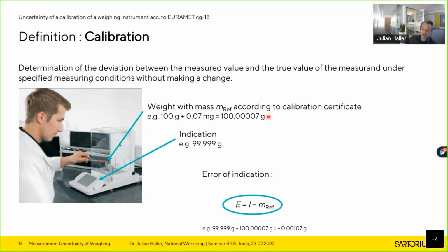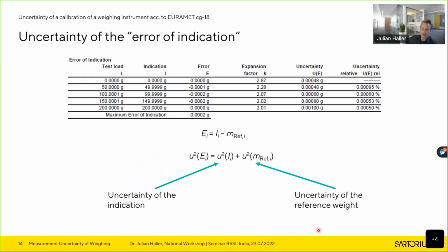And then you simply calculate, and this is the official result of a calibration, the error of indication, which is just the difference between these two values. So in this example, it would be this one minus this one, which is minus 0.00107 grams. So that is a calibration. And now we want to determine the uncertainty of this value.